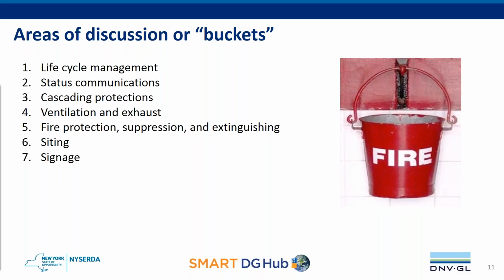The second area that we considered was status communications. Status communications include both normal operation status communications, so monitoring and maintaining the system utilizing the BMS, as well as status communications in case of alarms and alerts. So making sure that you're controlling your system within safe ranges, and if the system goes outside of those safe ranges, that you can have automatic stops in place or notifications of faults. The third item was cascading protections. This sub-bucket is really going to be one of the ones that has a lot of standards associated with it. And it's to ensure, if things do proceed, that they are prevented from cascading.